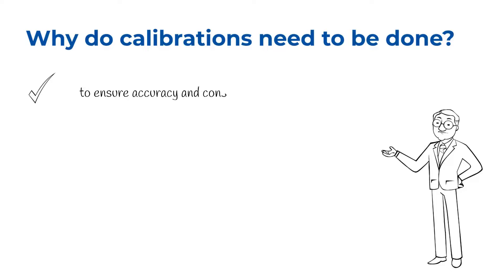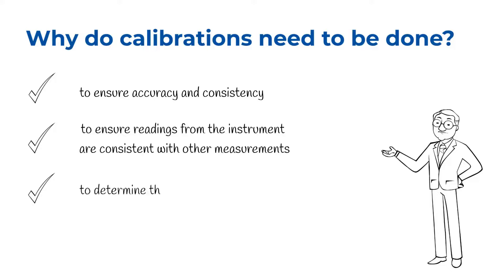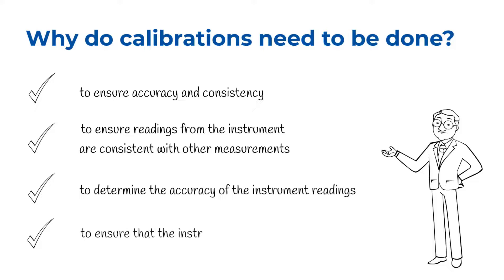The four most common reasons why calibrations are necessary are: to ensure accuracy and consistency, metrological traceability must be established and demonstrated, to ensure readings from the instrument are consistent with other measurements, and to determine the accuracy of the instrument readings by taking into account any potential sources of error.